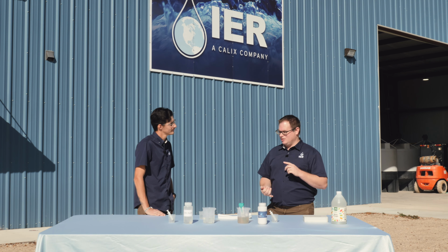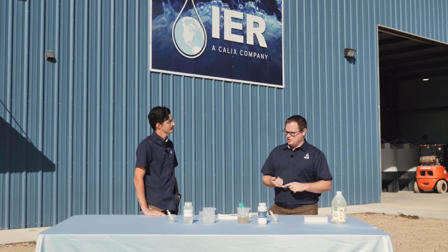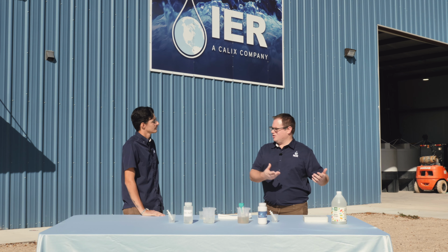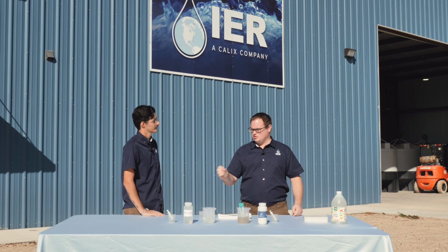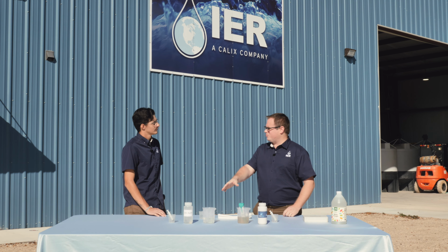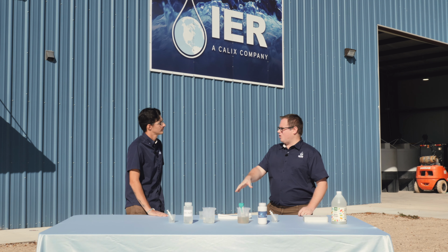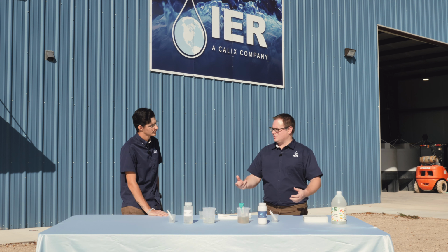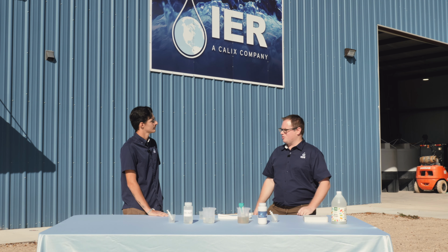Cool. They have seen when customers have switched from caustic soda to magnesium hydroxide, they have seen improvement in their treatment process. They've seen improvement in their solids handling. So generally it gives a better and a healthier product, because you also tend to be feeding it at the beginning of your treatment process, where caustic soda a lot of times is used at the very end to meet a permit requirement. So you're really just putting money down the drain to meet a permit quality, but you're not really using its advantages at other places in the treatment plant.